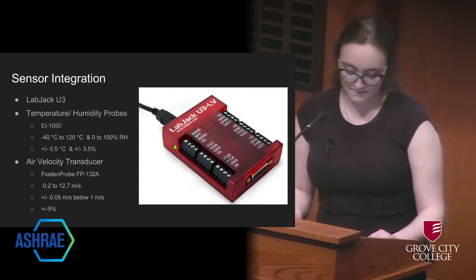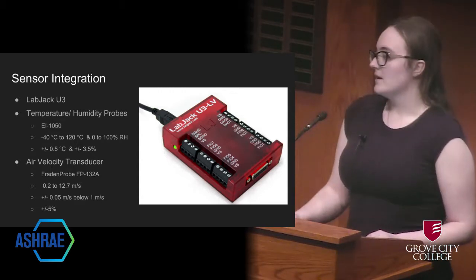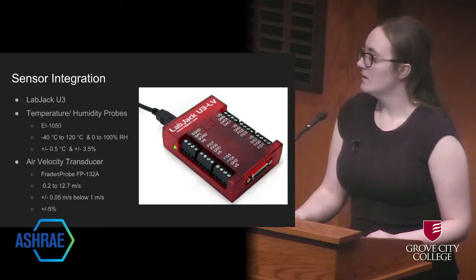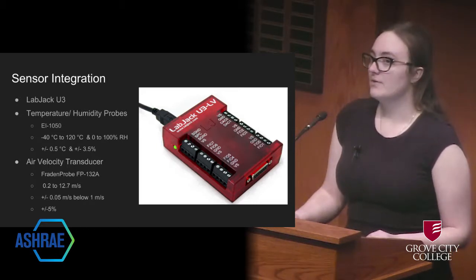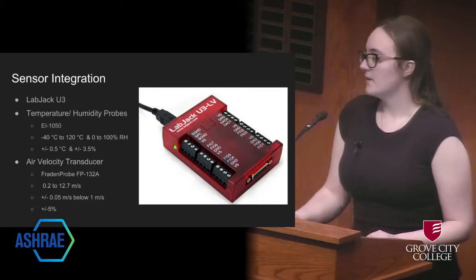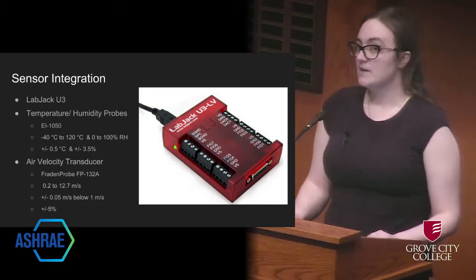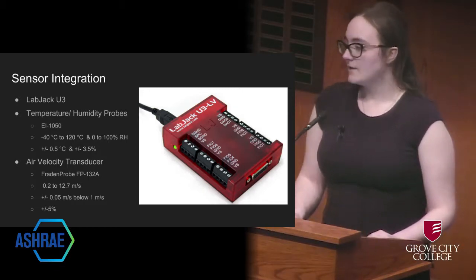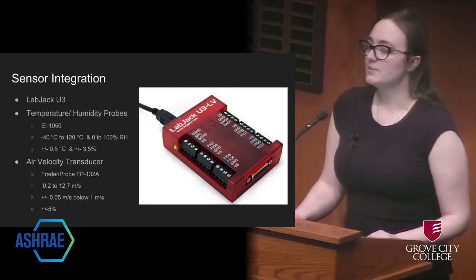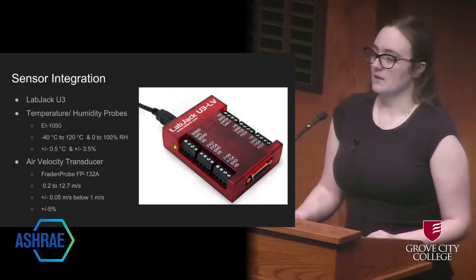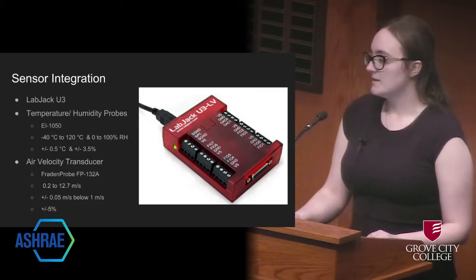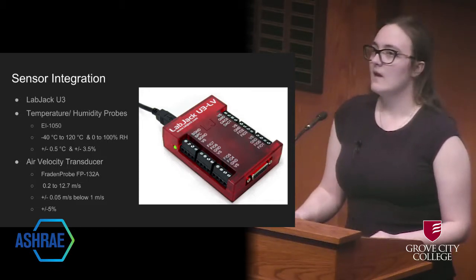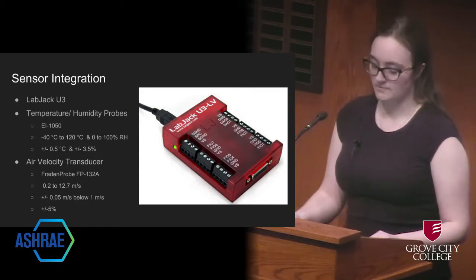The next sensor we added was an air velocity transducer, a FradenProbe FP132A. It ranges from 0.2 to 12.7 meters per second, with an accuracy of about 0.05 meters per second below 1 meter per second velocity. This also has an accuracy of about 5% after this calculation.